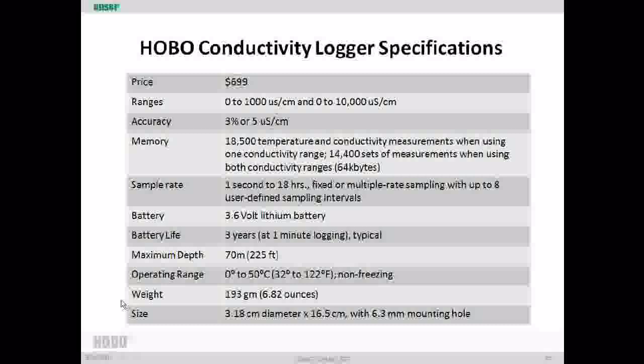So you can bring in the raw conductivity data and then compare that to your calibrated readings, and that'll give you a sense for how much sensor drift and how much fouling is affecting your measurements over time. If it's a fairly clean environment, you can stretch out the duration between having to go out and take calibration readings for your logger. If it's a harsher site and your measurements are changing fairly quickly, then you'll want to go out and take calibration readings more frequently.